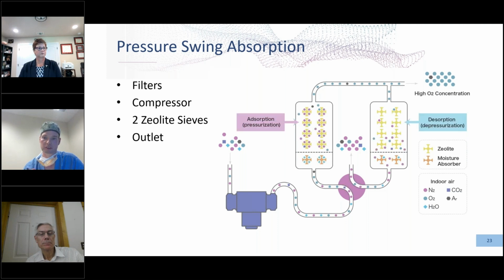As one sieve fills, it bleeds back some of the pure oxygen, not just to the outlets, but to actually wash out the previous sieve. And it just swings back and forth. So the air is going through one sieve, being filtered out there, and as it's filtering that oxygen, it's blowing out the previous sieve, all the old nitrogen that was in there, and that just gets released into the ambient air. And it just keeps switching back and forth, and that's how it can continuously give pure oxygen.